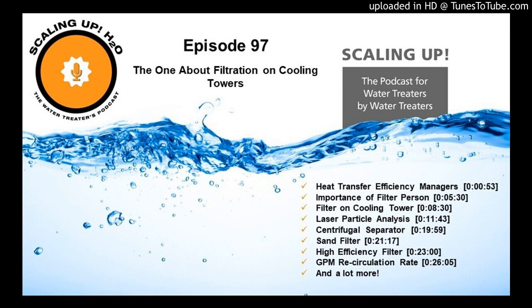Little by little, when people decided to put filters on the cooling water system, suddenly a water treater could kind of not do a perfect job. And frequently the water treater's only there maybe once a month or once a week. The customer's the one responsible for maintaining the chemical levels, and when they don't do their job, they blame the water treater. So clean water makes the water treatment chemistry work so much more easily. It kind of clears everything out so the chemistry can do its job.